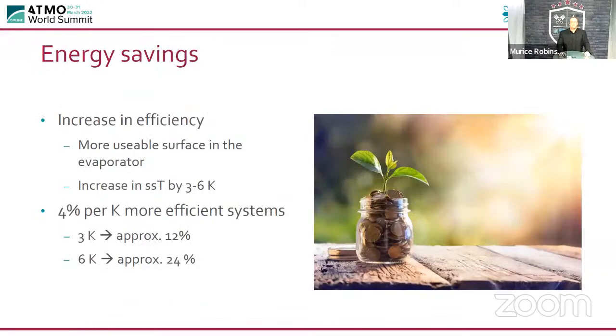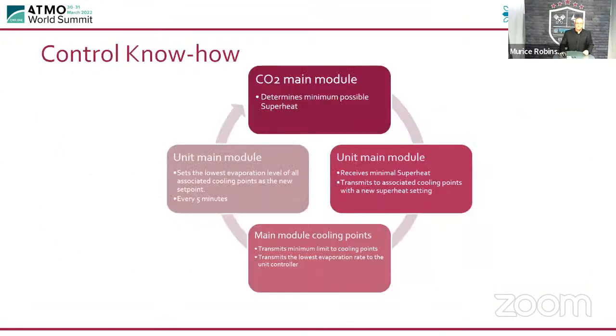So having a look at the energy savings, the increase in efficiency. You have a more usable surface area in the evaporator. So if you increase the suction temperature by 3 to 6 K, this is what happens. As a rule of thumb, it's 4% per K more efficient in every system. So if your suction temperature rises by 3K, you can expect an average of 12% energy saving. If you increase it by 6K, you can expect a 24% energy saving. So depending on how far you can push the system is how much energy saving you'll actually achieve.